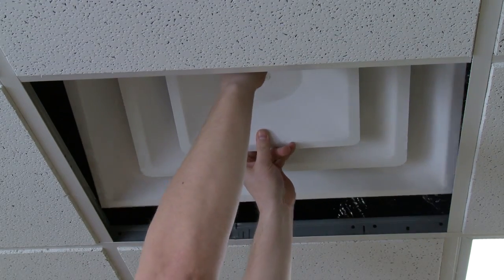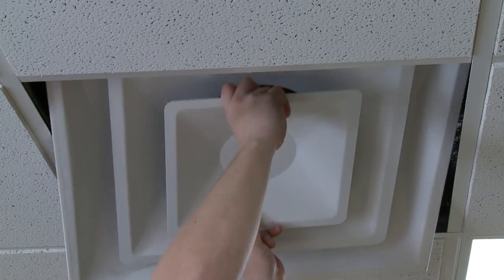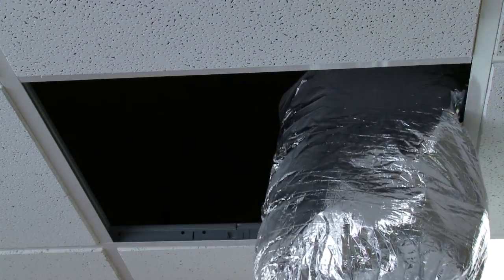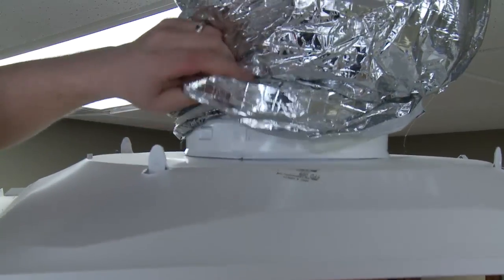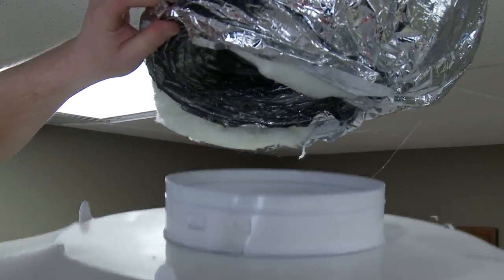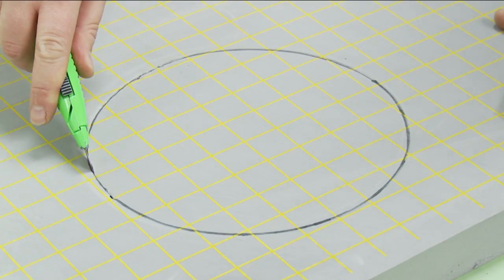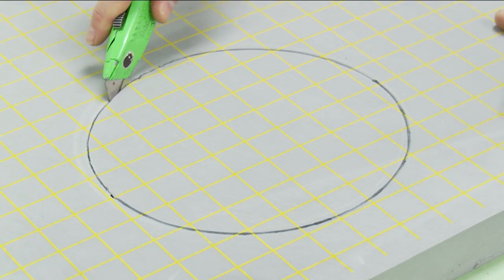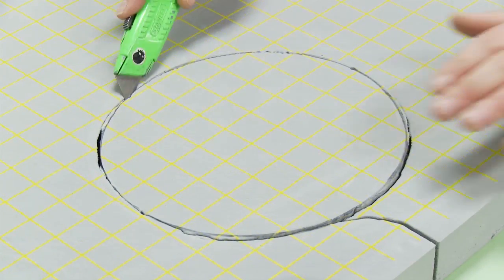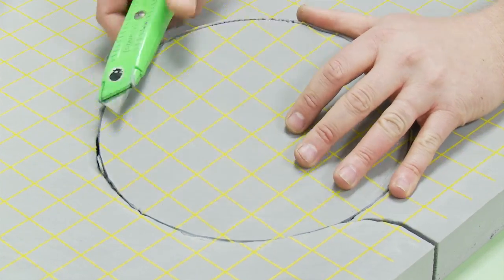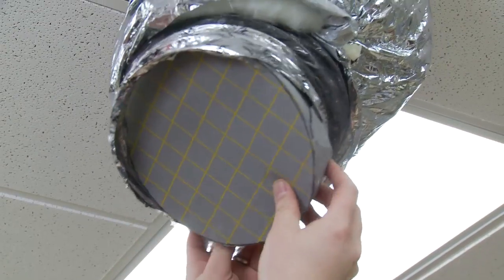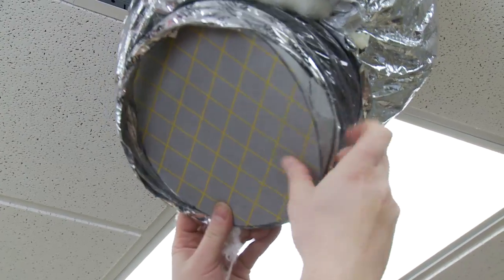Diffusers will need to be removed for blocking. It is critically important that all blocking is airtight. Blocking can be done several different ways. General best practice is to use closed cell blocking foam. The foam should be cut 1/2 inch oversized in both length and width of the opening being blocked. Then stuffing the block into the hole will ensure the airtight fit needed.